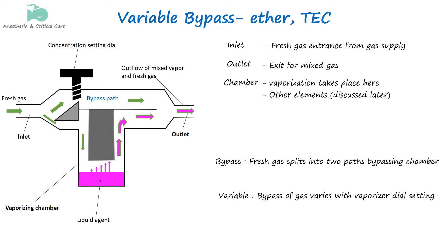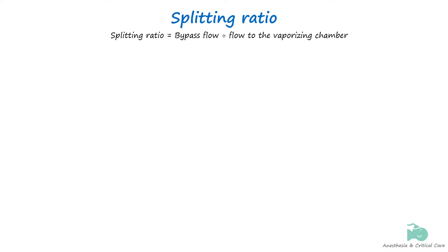For this reason, it is also called concentration calibrated. As we have seen, the variable bypass method splits the gas into two streams. The ratio of fresh gas flow bypassing the vaporizing chamber to the flow passing into the vaporizing chamber is referred to as the splitting ratio.